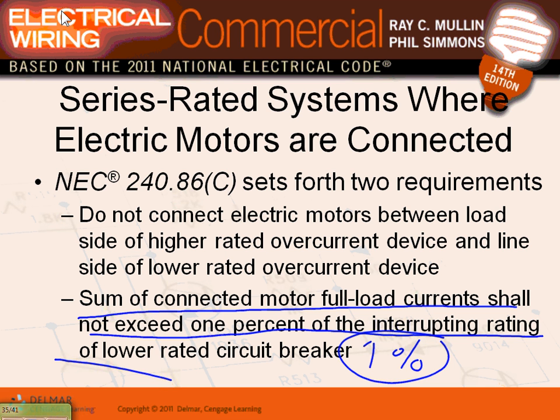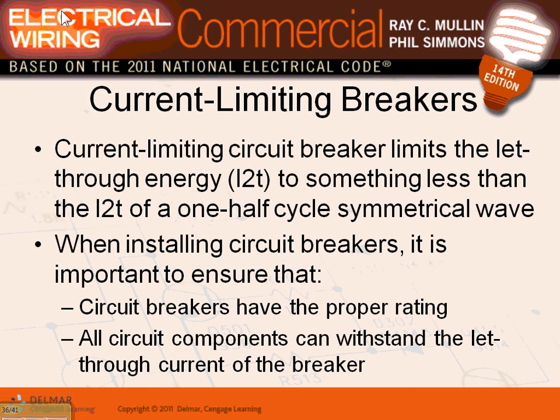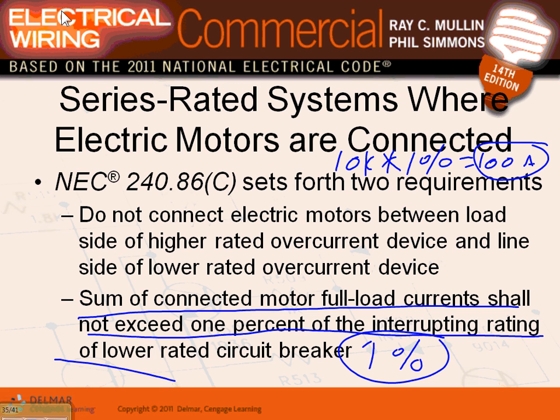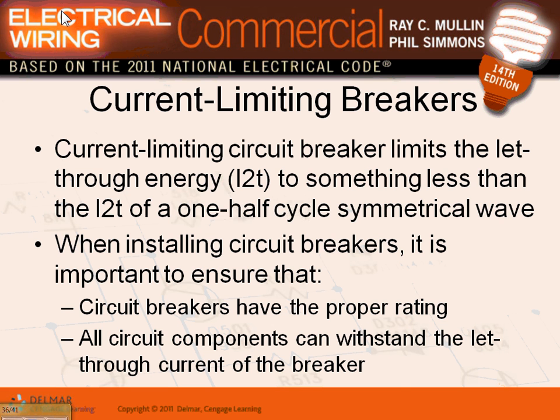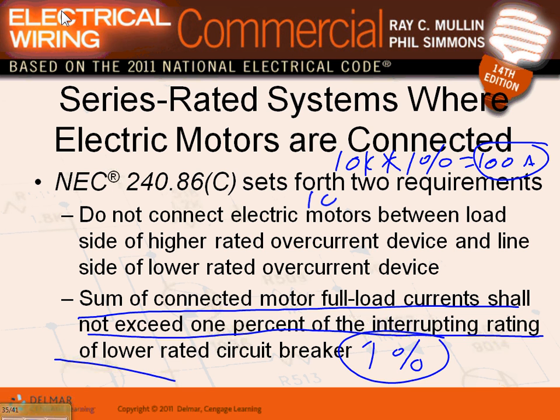Come on, what is that? 1%. It's Monday, huh? That's 100. So 10K times 1% equals 100 amp, right? You guys say so, 100 amp. So when you add the full load current of all the motors, you don't want them to exceed 100 amp. This is okay. If it exceeds, then it's fully rated.